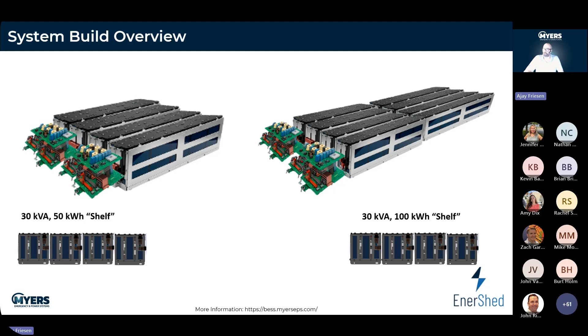And then we've put those into enclosures, and we've got 4 different sizes of enclosure. This is an AC coupled energy storage system. We do all the combinations of these different shelves in the enclosure, but what we've done here is you can populate that enclosure with as many or as few of these shelves as you need. And so if your customer wants a 60 kVA system, you can provide them a 60 kVA system. If your customer wants a 90 kVA system, you can provide them that. And you can do that every 30 kilowatts. That's unique in the industry.